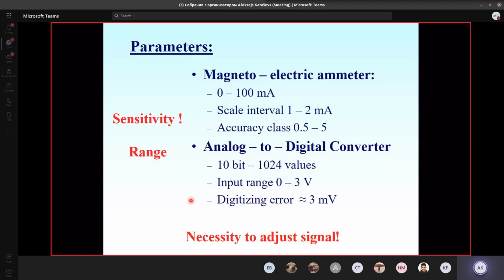And usually the accuracy of such budget class magnetoelectric meters is from 0.5 up to 5. No, for 5 it's quite big. Yeah, 5 is 5% of the range. For 100 milliamps, the accuracy is about plus or minus 5 milliamps, so it's not so accurate a device. But for accuracy class 0.5, it's fine. For the 100 milliamp device, we have a measurement uncertainty of around 0.5 milliamps. That's quite good.